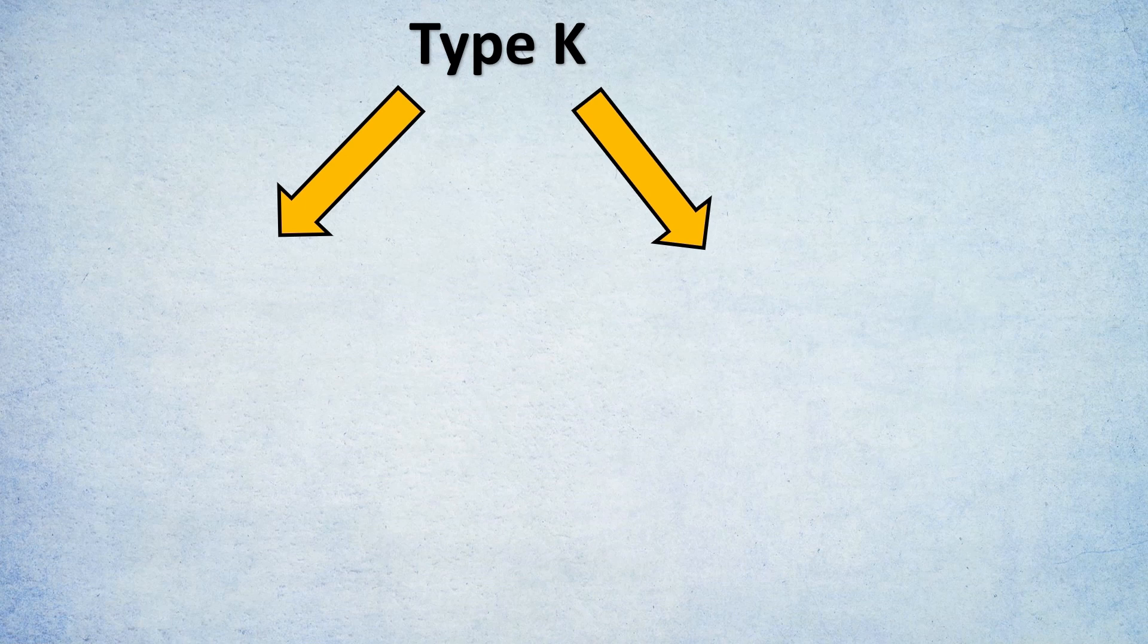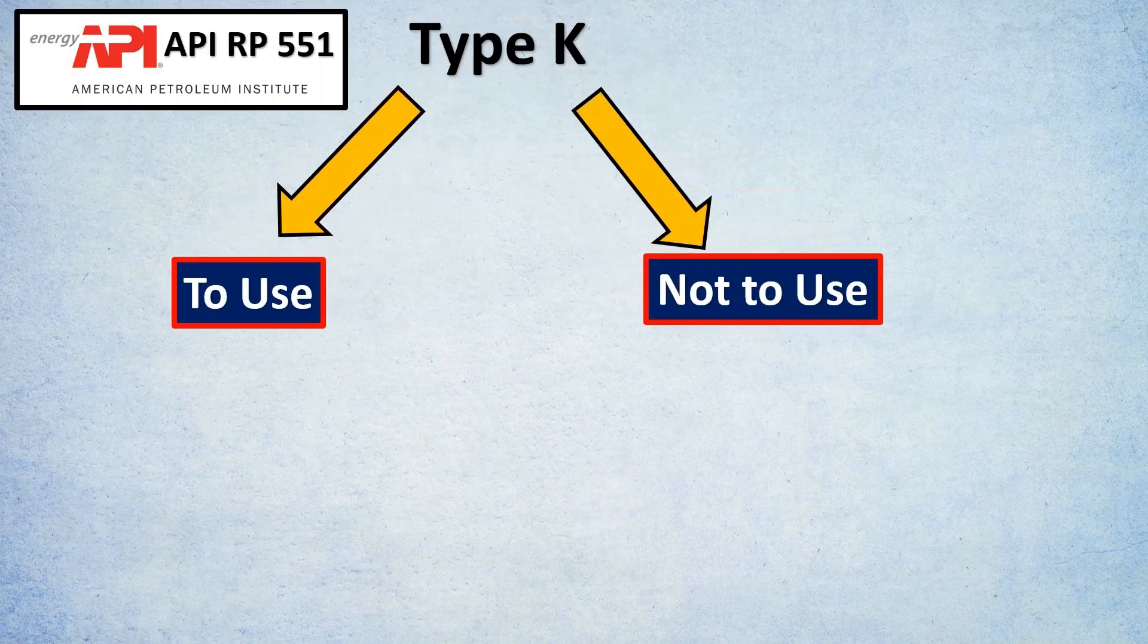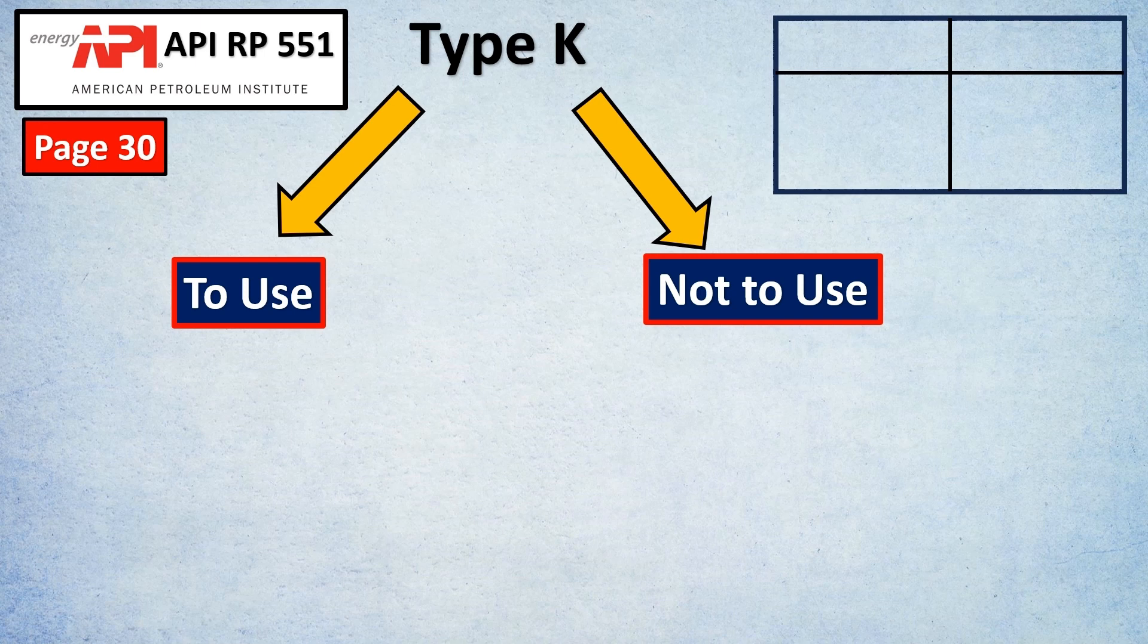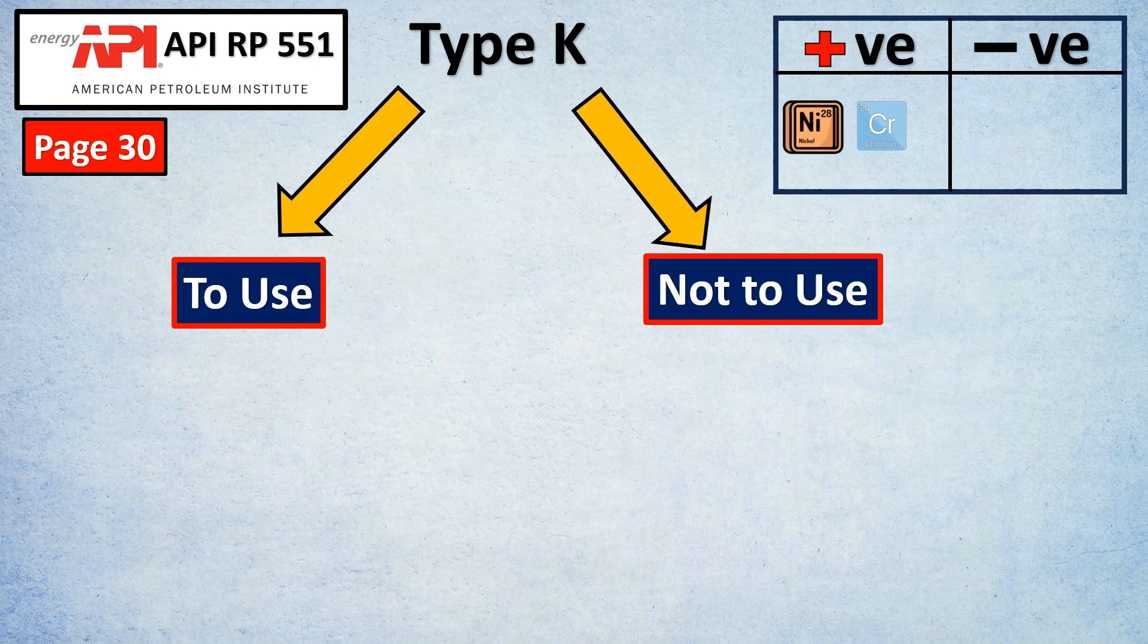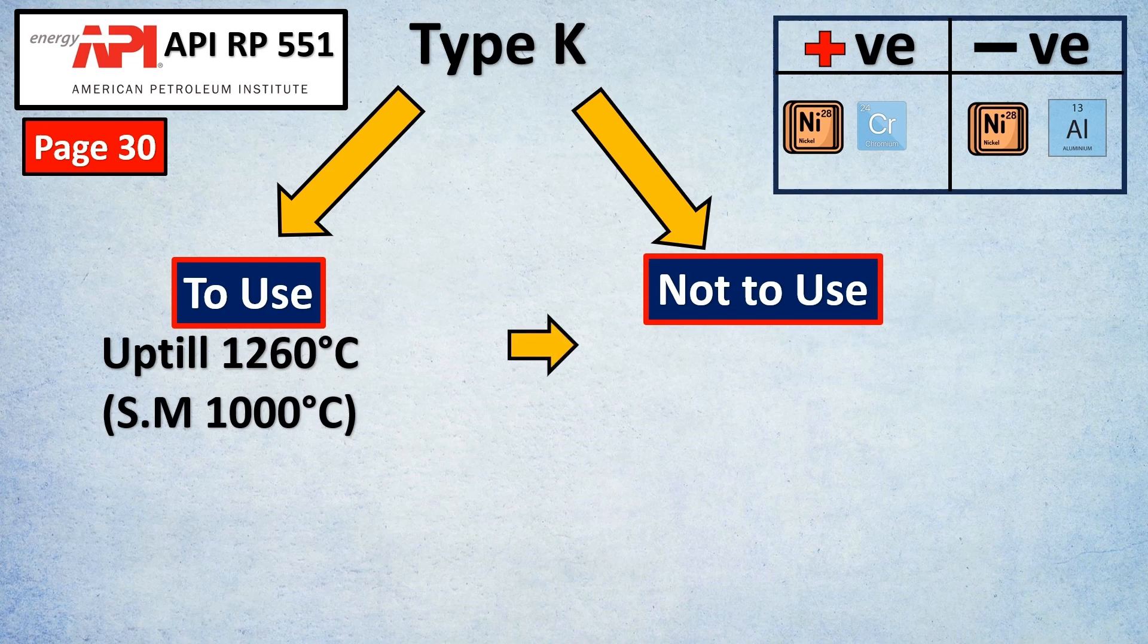The first thing is type K thermocouples. Type K are the most widely used thermocouple. So we will look at when to use and when not to use these thermocouples as per API RP 551 page number 30. So first thing is before we start with K type, let us know what is K type made up of. So K type has the positive side and the negative to it. So the positive is made up of Nickel and Chromium and the negative is made up of Nickel and Aluminium to it. This can usually be used up till 1260 degree Celsius. As a safety margin you can say 1000 degree Celsius is what I personally recommend.